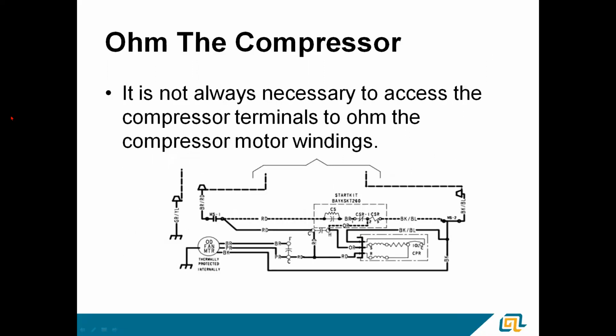You don't always have to get to the compressor terminals to ohm the windings. We all know what that's like. You got to pull the top off, you got to pull the fan off, you got to get the compressor terminal box cover off. It can be a real bear. So I myself never had an issue with ohming out those compressor windings right from the wires. Here you got your run winding, this red wire coming off the capacitor. The orange wire coming off the capacitor is your start winding, and the black and blue wire coming from the contactor is your common. So you can ohm it out there.